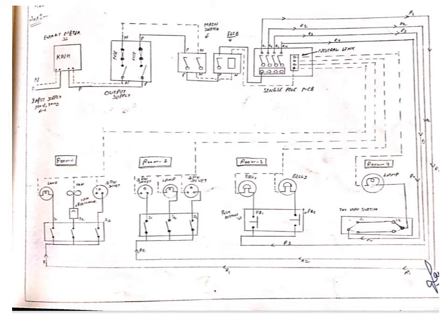Then there is the ELCB, that is the earth leakage circuit breaker. The MCB is used for protection against short circuits and overload conditions. But for leakage currents, these MCBs will not detect those conditions. So phase and neutral will go to the ELCB, which will protect our installation from leakage currents, that is milliampere rated currents. For example, there may be leakage between phase and neutral, and it will go to the body of the equipment that we are operating. So to save ourselves from electric shocks caused by leakage currents, the ELCB will protect us.